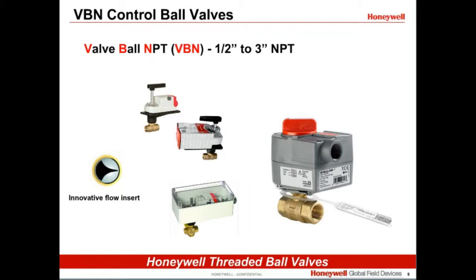VBN control ball valves are used in closed-loop, non-oxygenated systems. They can control chilled water and glycol mixture down to -22 degrees Fahrenheit and hot water up to 250 degrees at 250 psi. They are available in a wide range of sizes from 0.33 to 109 CV. The highest CV offered in a valve size is usually a full port ball. That means it does not contain a characterized insert and has a linear characteristic. This is recommended for two-position control applications.